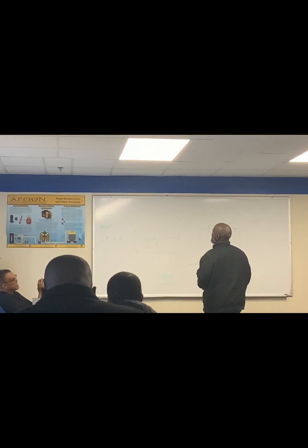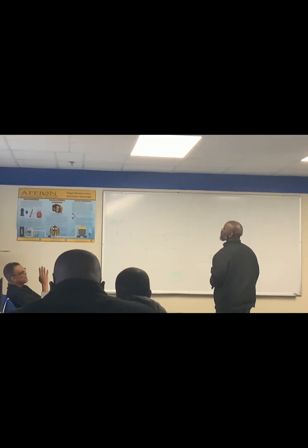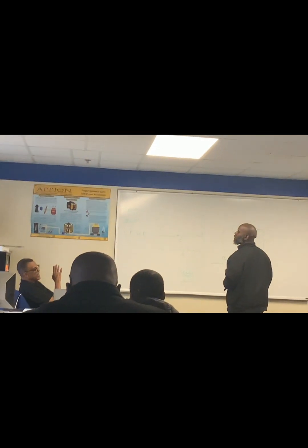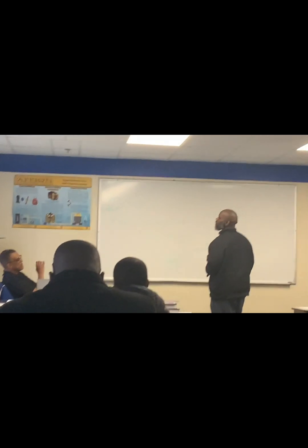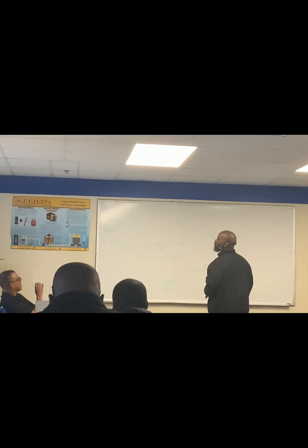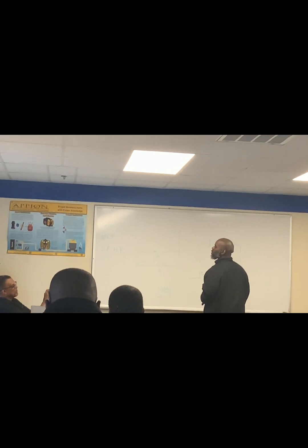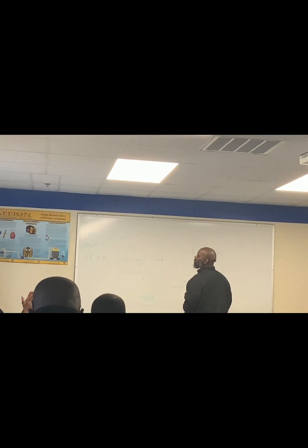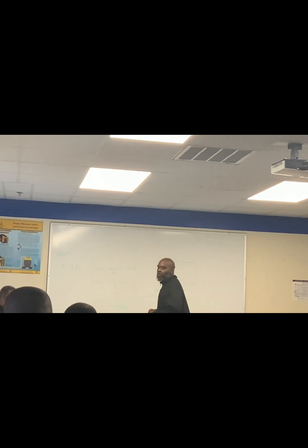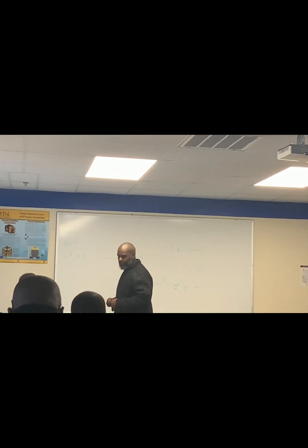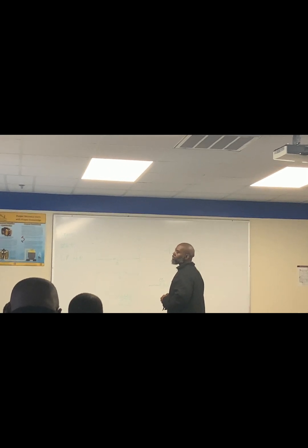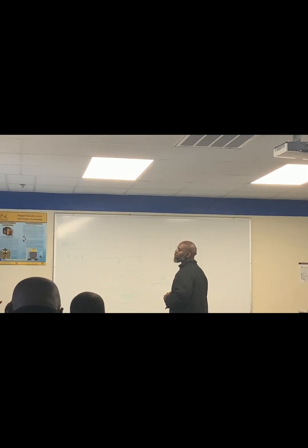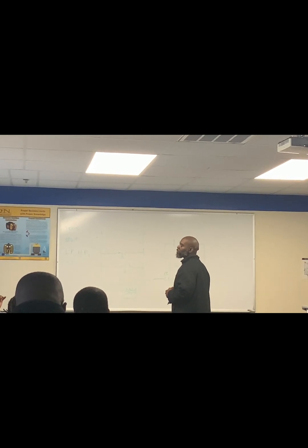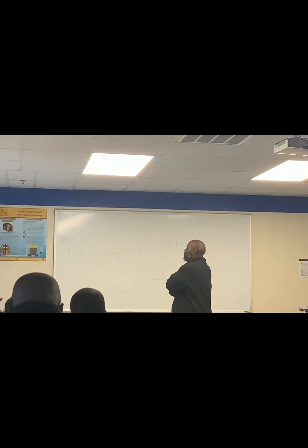What that does is tell you what circuit to troubleshoot. I have to come from the thermostat and make sure I have 24 volts. The colors I asked you about would actually be in the air handler on that board. Those are the colors that respond to the thermostat, to what position we put it on. It energizes the circuit, closes switches pertaining to air conditioning, and then the outdoor unit will run.